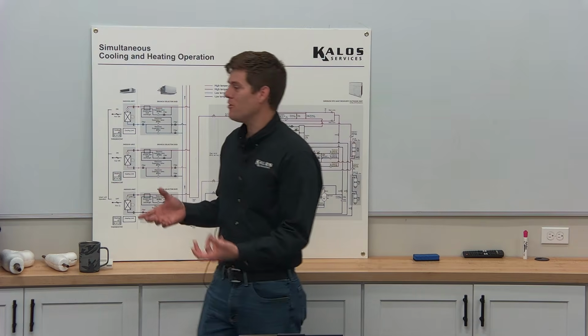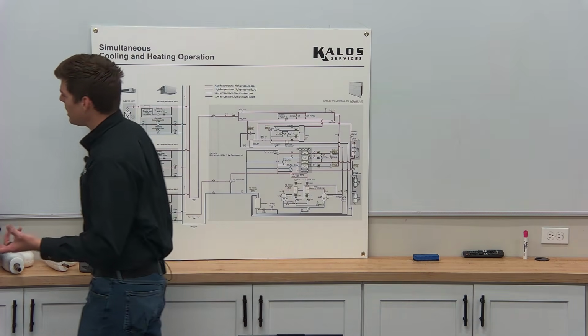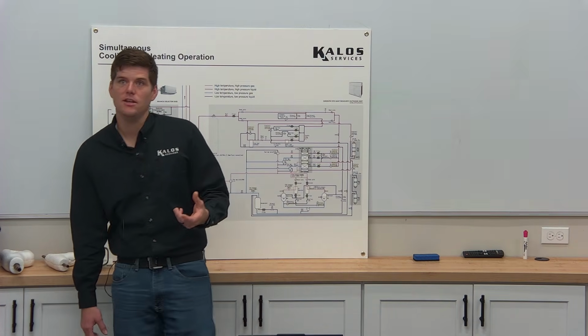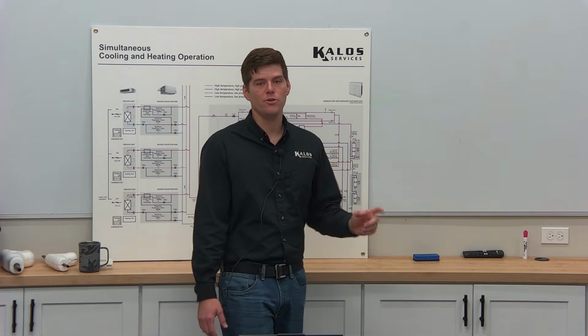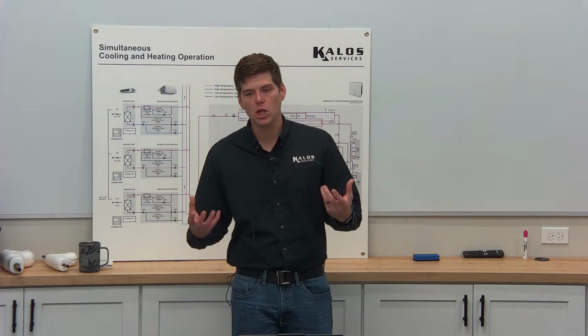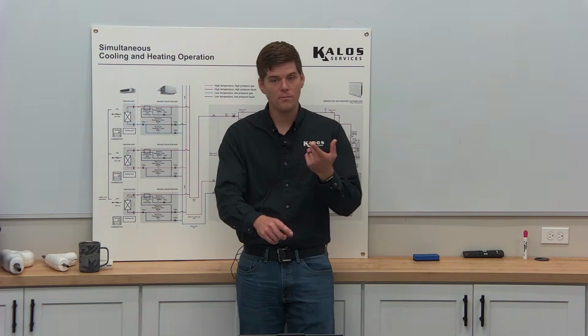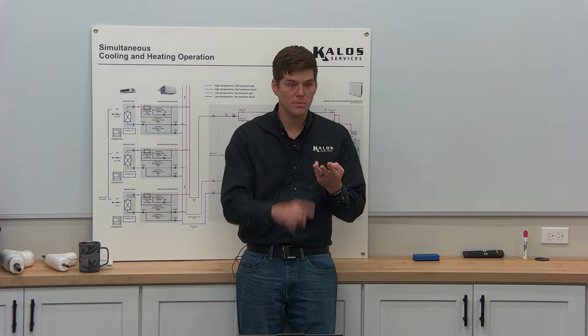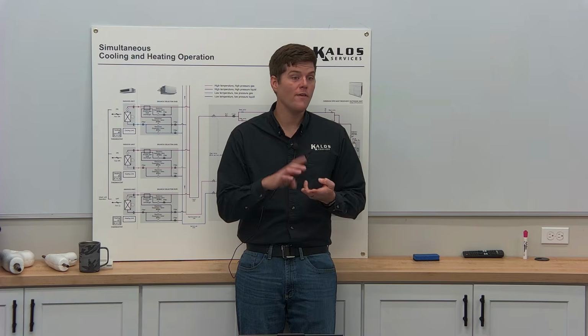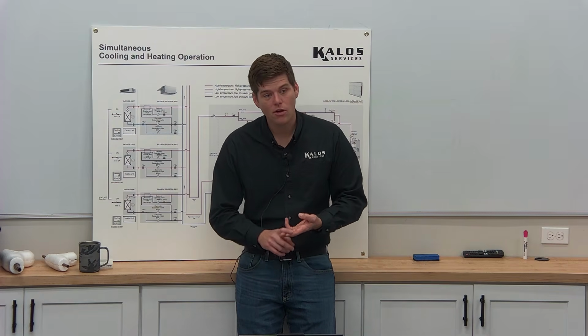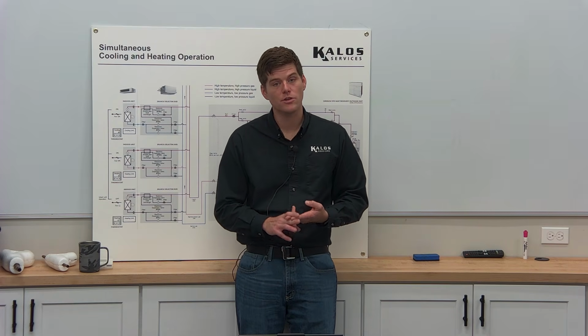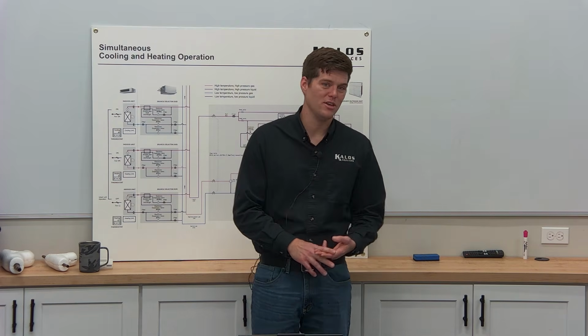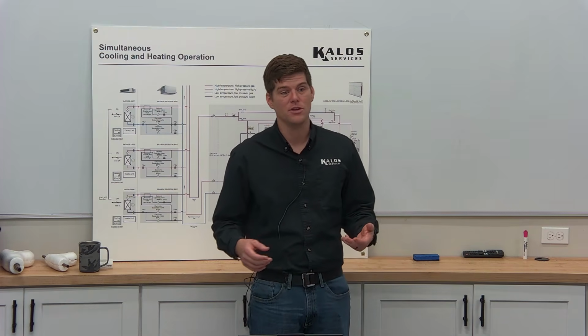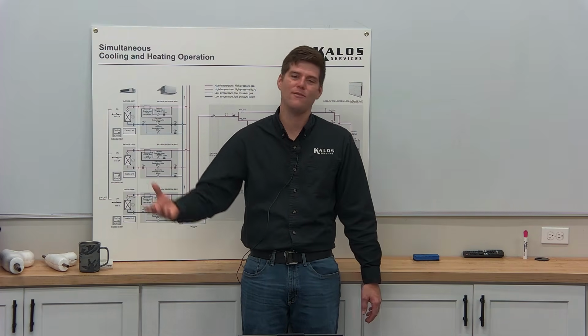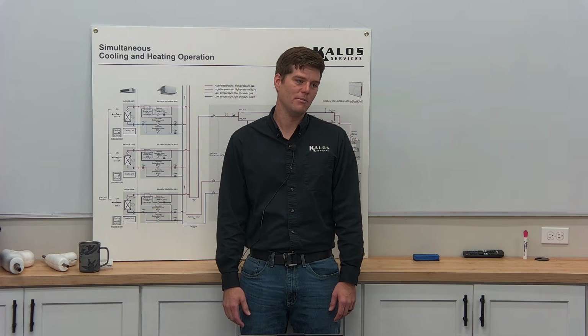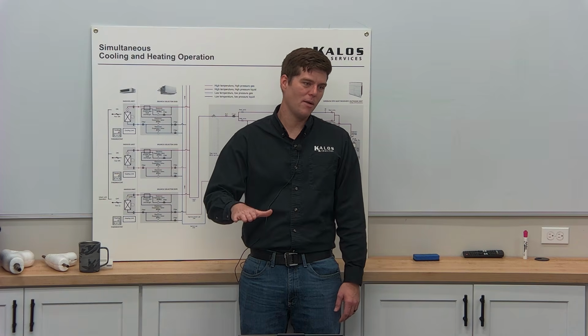Almost every single VRF unit, mini split, I don't care who makes it, if it looks like these bottom 4 units there, they're serviceable from below. That means drain pan, sensors, expansion valves, whatever it may have, fan motors, they're all serviceable from below. So if you are installing one of these, if you are servicing one of these and you come across it and you have to open it up because you think something's wrong or it's making a heck of a racket, right?